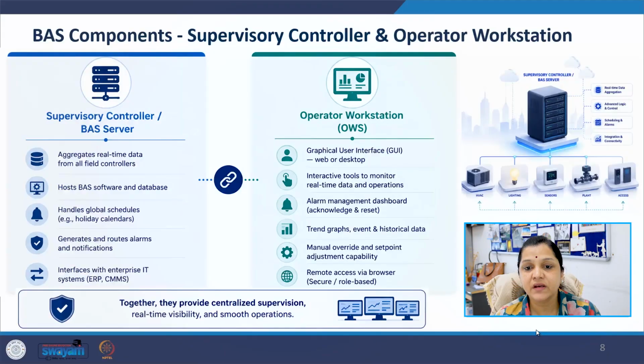So next is supervisory controllers and operator workstations. The supervisory controllers or BAS servers aggregate information from all field controllers within the building. It hosts BAS software and databases, manages global schedules, generates alarms, and archives trend logs for analysis and compliance.